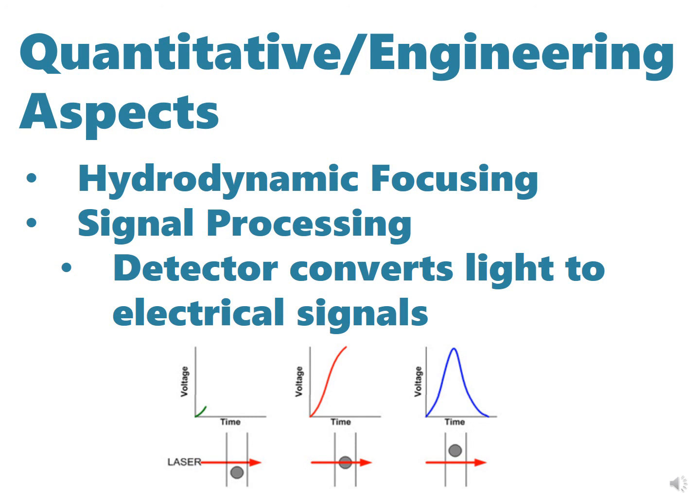Electronics quantify the electric pulse by calculating the height, area, and the width. The height, area, or maximum and integral respectively are used to measure signal intensity because their magnitudes are proportional to the number of photons that interacted. The width, on the other hand, is proportional to the time that the particle spent in the laser. It can be used to distinguish doublets from singlets.